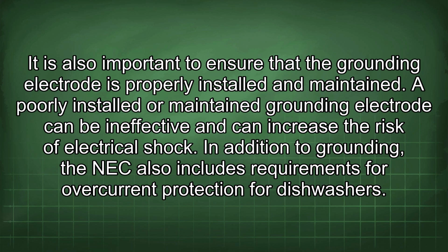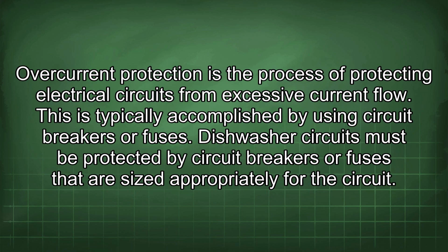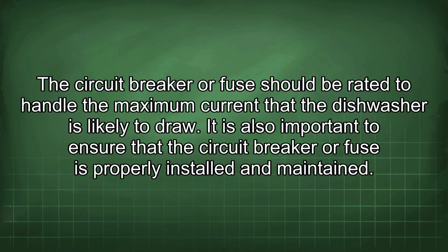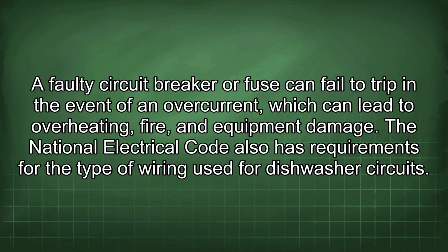In addition to grounding, the NEC also includes requirements for overcurrent protection for dishwashers. Overcurrent protection is the process of protecting electrical circuits from excessive current flow. This is typically accomplished by using circuit breakers or fuses. Dishwasher circuits must be protected by circuit breakers or fuses that are sized appropriately for the circuit. The circuit breaker or fuse should be rated to handle the maximum current that the dishwasher is likely to draw. It is also important to ensure that the circuit breaker or fuse is properly installed and maintained. A faulty circuit breaker or fuse can fail to trip in the event of an overcurrent, which can lead to overheating, fire, and equipment damage.